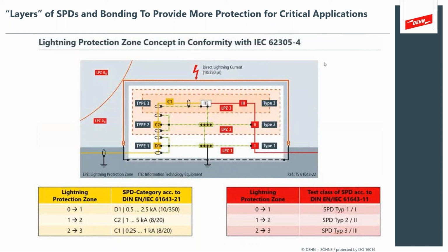We have a question where Damien asks about bonding and separation, and Damien, I think you're asking if there are any advantages of bonding and separation, for example, with a PV panel. Mark, I can just quickly mention that we had a discussion about separation distance and bonding, a bonded system and an isolated system, in our previous webinars, and what we mentioned there is it's all about where you want to inject lightning current. In a PV installation, you don't want lightning current injected into your inverters and into your frames and even into the sensitive communication systems that you have in large PV fields.